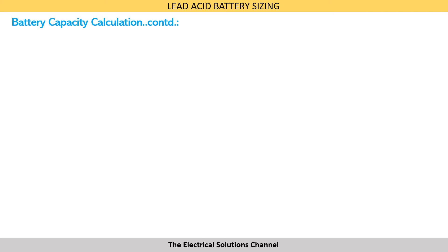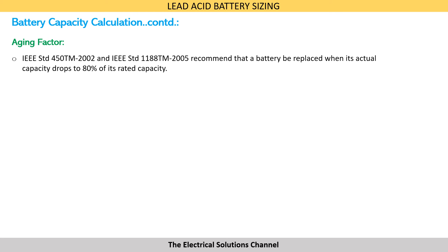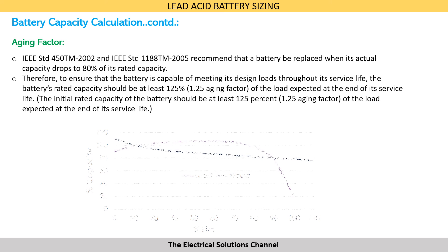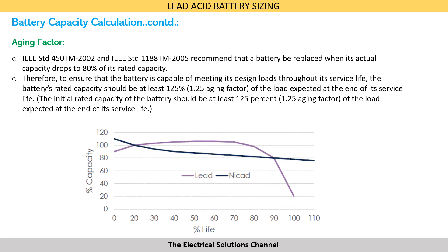Aging factor: IEEE 450 and IEEE 1188 recommend that a battery be replaced when its actual capacity drops to 80 percent of its rated capacity. Therefore, to ensure that the battery is capable of meeting its design load throughout its service life, the battery's rated capacity should be at least 125 percent - that is, an aging factor of 1.25 - of the load expected at the end of its service life.